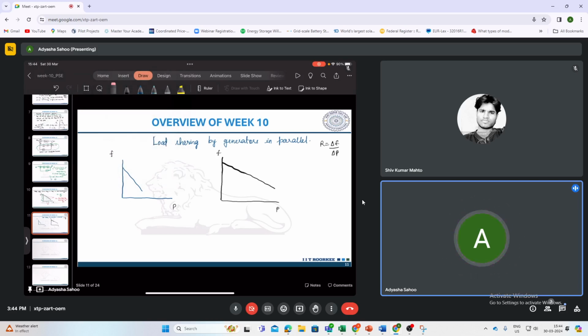Okay. So let's say initially they are operating at a certain point F naught, and the load shared by them is, let's say, P1 and P2. So let's say this is in steady state, and let's say there is an increase in load. So increase in load means the generation has to increase. In what proportion? Let's say there is a 100 megawatt increase in load. So how will this 100 megawatt be shared by these two generators? Will they share equally, or will the first generator share less load or more load? That will be governed by their droop characteristics.